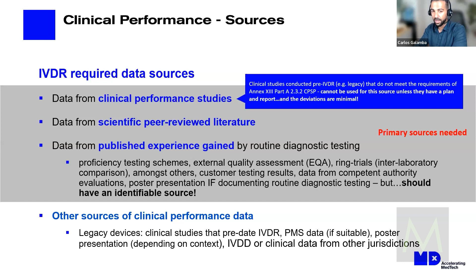The only other thing I would say, and this is a question that we see quite often, is about clinical studies. A lot of the clinical performance studies were done pre-IVDR, before the IVDR was in place. In a lot of cases, they will not meet the definition of a clinical performance study under Annex 13, Part A, because that has a list of several requirements that need to be met for a study to be considered a clinical performance study protocol. So it's ambiguous whether you can use that data as a clinical performance study. You would essentially need to do a gap analysis on your study and see if most requirements of the IVDR are covered. If there are significant gaps, you may not be able to use that clinical study as a source of clinical performance data for an IVDR submission. So just something to take into account.